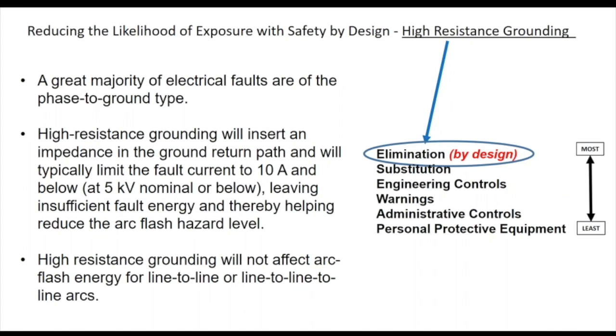All those things are electrical parameters that would need to be discussed going forward in your place of business. But it would leave insufficient fault energy and thereby help reduce the arc flash hazard levels, which is fabulous. High resistance grounding will not affect arc flash energies line to line or line to line to line arcs, all three phases. But it is elimination by design.